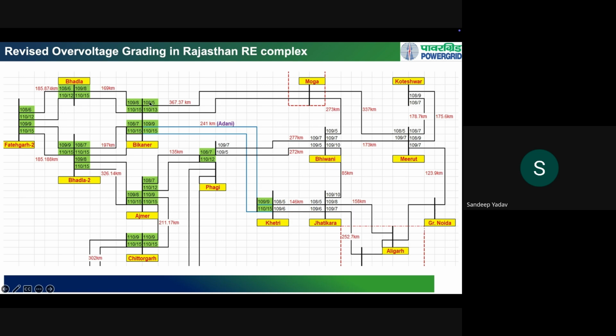What we did is that we implemented a much better grading strategy in the entire region. Now the over voltage protection tripping times start from 5 seconds, and go 5, 6, 7, 8, up to as high as 15 seconds. By that time, because a few of the lightly loaded lines would have tripped, the transmission lines with higher delay will survive. So we increased the over voltage protection tripping time delay from the initial value of 6 or 7 seconds to, in some cases, 12 seconds, and in other cases 15 seconds. After doing this, the possibility of a region-wide blackout was much lesser.